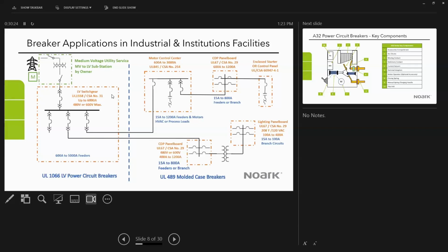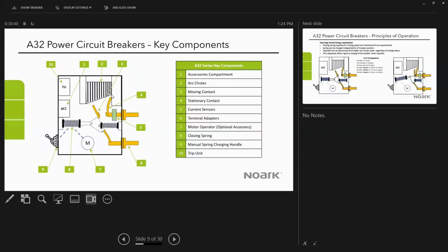So just to recap, for the UL 1066 type breakers, they primarily show up in low voltage switchgear and as the main devices in low voltage switchboards. Okay. So just the next couple of slides here are getting a little bit deeper into the construction of a power circuit breaker. And by the way, we call them power circuit breakers. Often they're called air circuit breakers. There's a few different names for these devices. But for our purposes today, we'll either call them a power circuit breaker or an air circuit breaker, or an ACB, as it's commonly known.